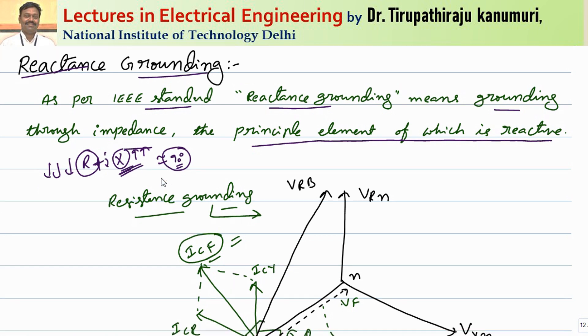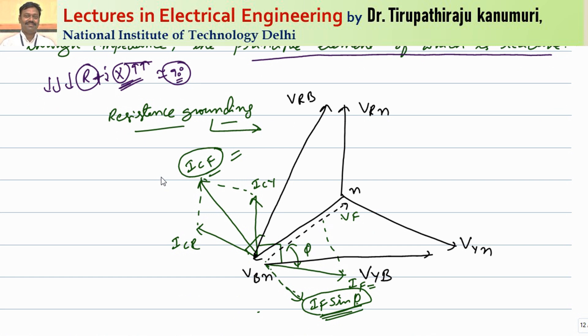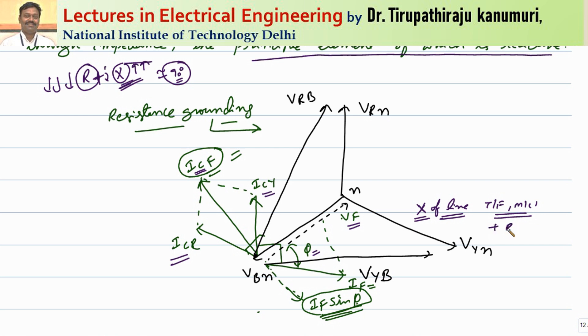Before going to reactance grounding, let us review resistance grounding from the last class. In resistance grounding, capacitor currents ICR and ICY are present, and the resultant current ICF is due to the capacitive currents of the healthy two phases. Because of the faulty phase voltage, the current lags by angle phi, which is decided by the reactance of the transmission line — transformers, machines, and all elements — plus the resistance connected in the neutral circuit.